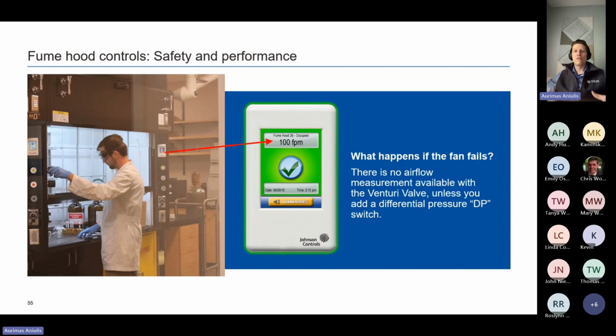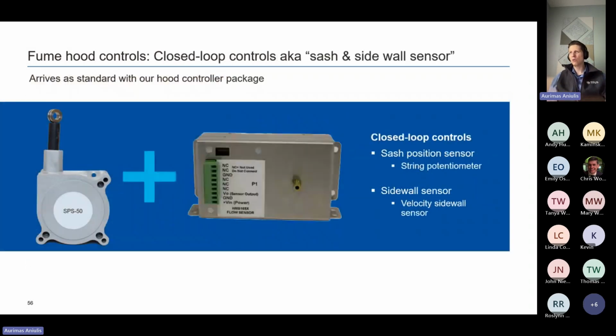But that does not account for fume hood loading in the workspace: Bunsen burners, big ovens, racks with beakers and other equipment. So you really want something that will, in real time, tell you the fume hood conditions and help you throttle the exhaust on that fume hood in order to maintain a safe face velocity. So in addition to the sash position sensor, we also highly recommend using the sidewall differential pressure transducer, or sidewall sensor, which is what we use to measure the conditions inside of the fume hood workspace in real time. This gives us a closed loop control sequence for fume hoods. This ensures safety, reliability, and efficiency.